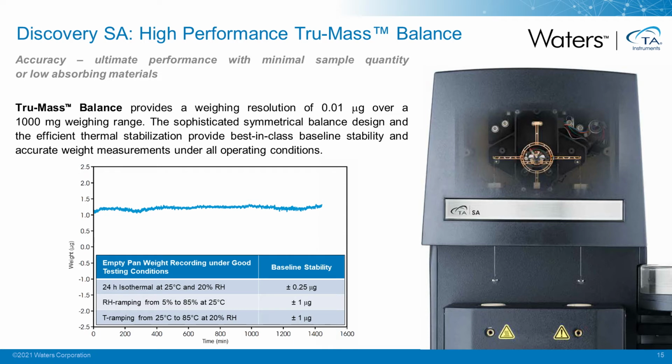Now, since these experiments are very, very long, of course you want to have very stable weight signals so that you can be very sensitive to changes in weight that occur. You don't want the balance drifting either over that time period.